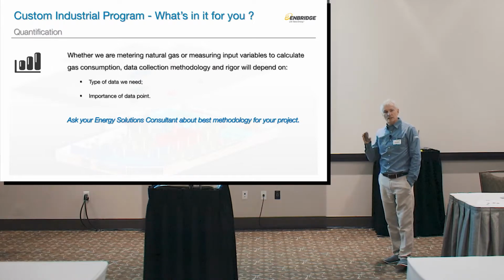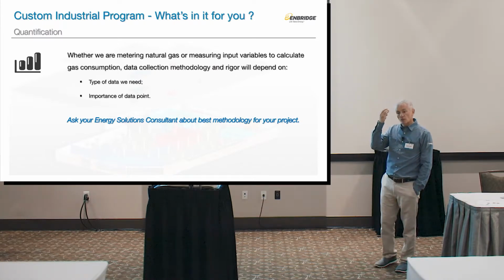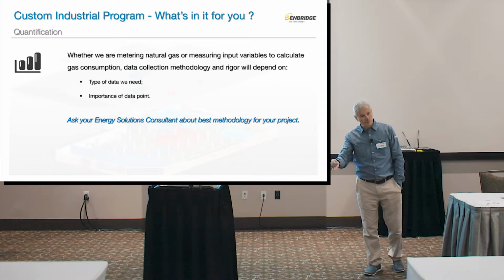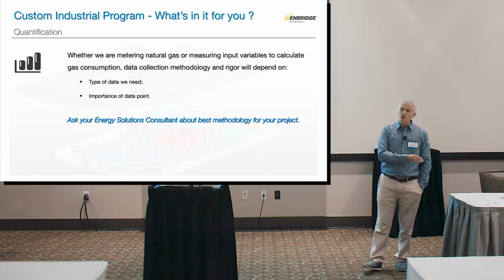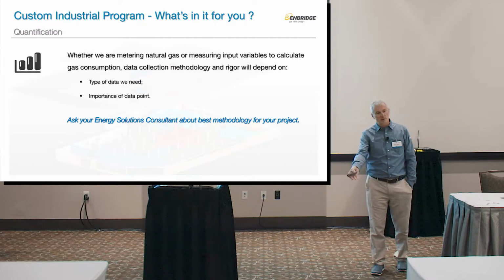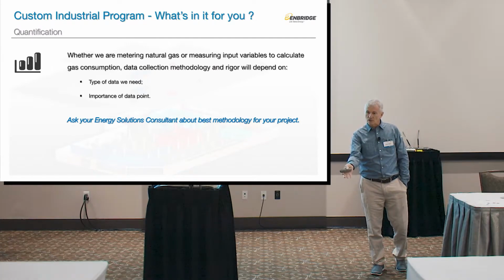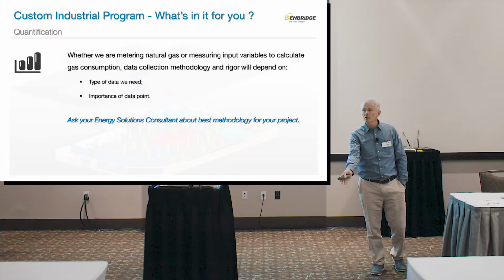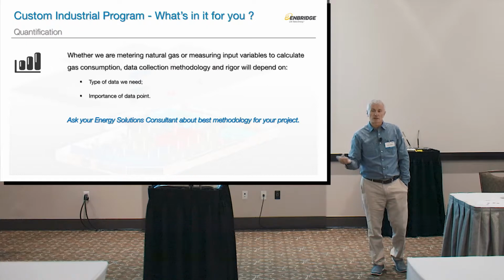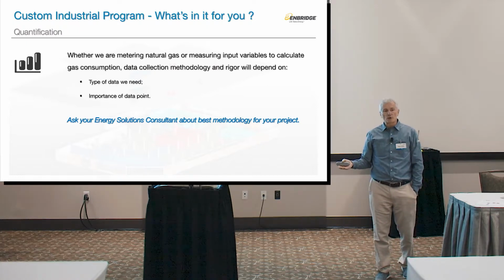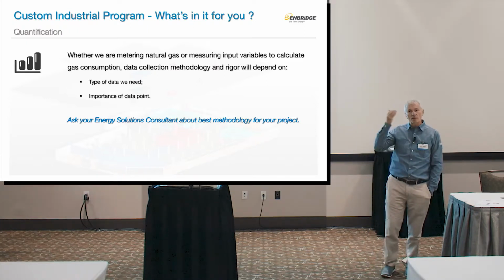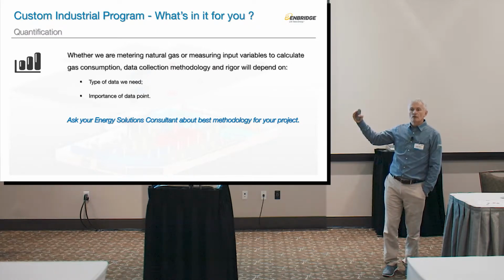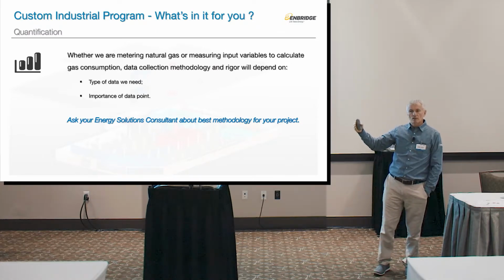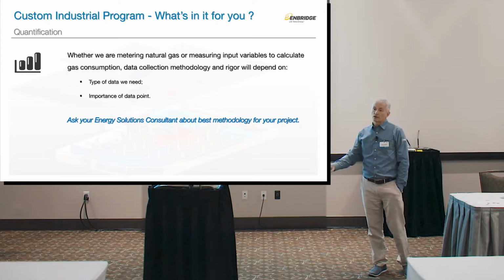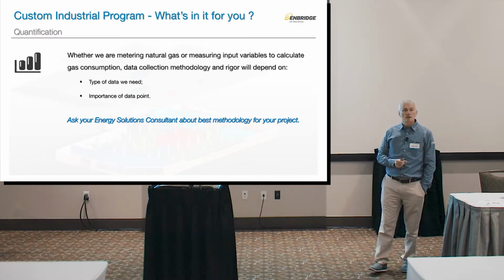I cannot tell you how many times we had customers wanting to replace a water heater, telling us they'd save X amount because their water meter uses this much water. We went and put an ultrasonic water meter on the pipe and left it there for a week at no charge to the customer. We read the data, and it turned out they used one tenth of what they thought, because all they could think of was the peak. After 15 minutes of peak, they use next to nothing. So we said, look, maybe the money is better spent somewhere else.